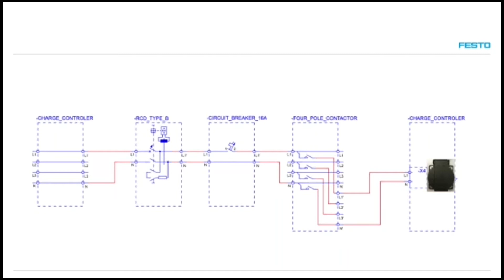On the control or sensing connections side, the low power connections, we connect specific terminals of our charge controller, 15, 16, and 17, to the 4-pole contactor, RCD type B, and circuit breaker 16A. But we're not connected to the power plug of these devices, rather to the control signal—the normally open or normally closed contacts that tell us their current status. Based on this signal, the charge controller knows if the circuit is safe to power the car or not.